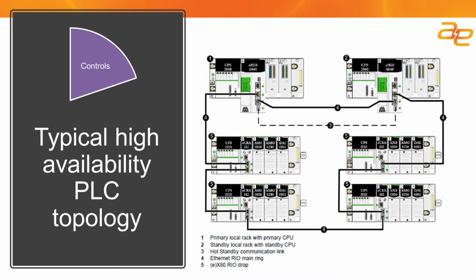You typically have 1 or more controllers, but typically 2 controllers. And those controllers do not contain what we call any I/O modules or input-output modules. They are strictly in place to execute the control logic for the overall system. But then those controllers are linked to remote I/O, input-output modules, that reside outside of the primary racks. And you can distribute that I/O throughout your facility depending on where the equipment is. You can distribute it in a way that reduces the amount of cabling that you have to pull within your facilities. But again, there's a lot of flexibility in terms of that design.